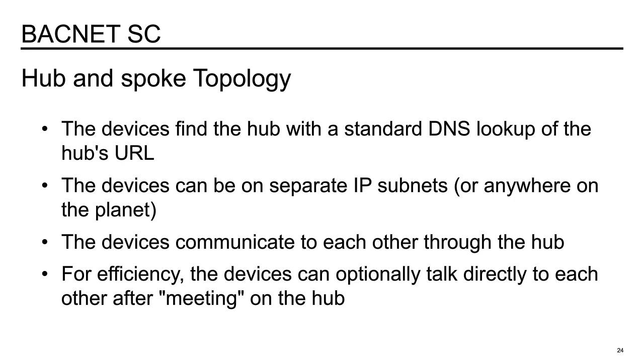The devices communicate to each other through the hub, and we've got some diagrams coming up that we'll look at. And then for efficiency, the devices can actually talk directly to each other after meeting on the hub. And like I mentioned before, what ends up happening is the BACnet SC hub becomes that trusted middleman that we talked about before that relays the messages.